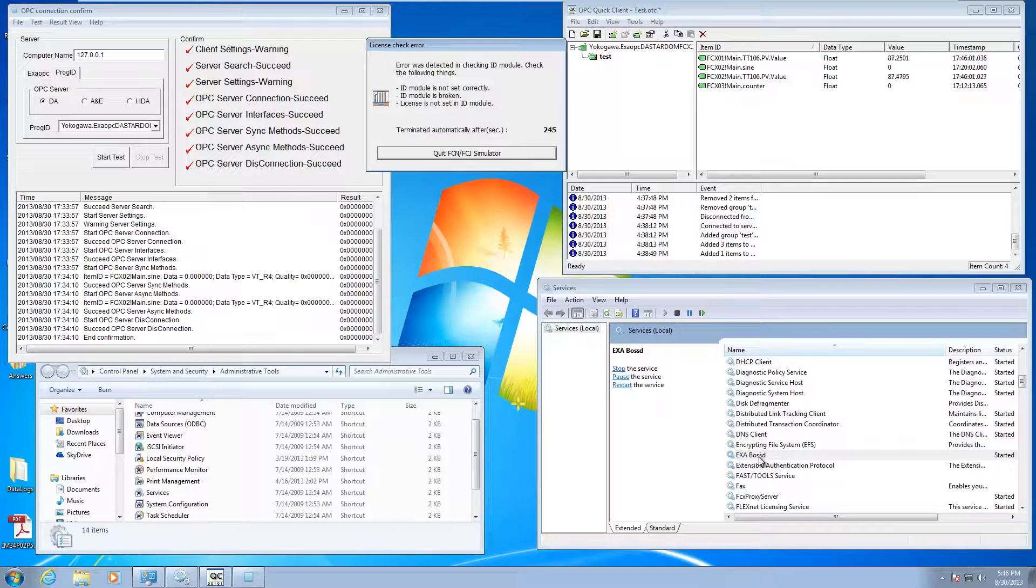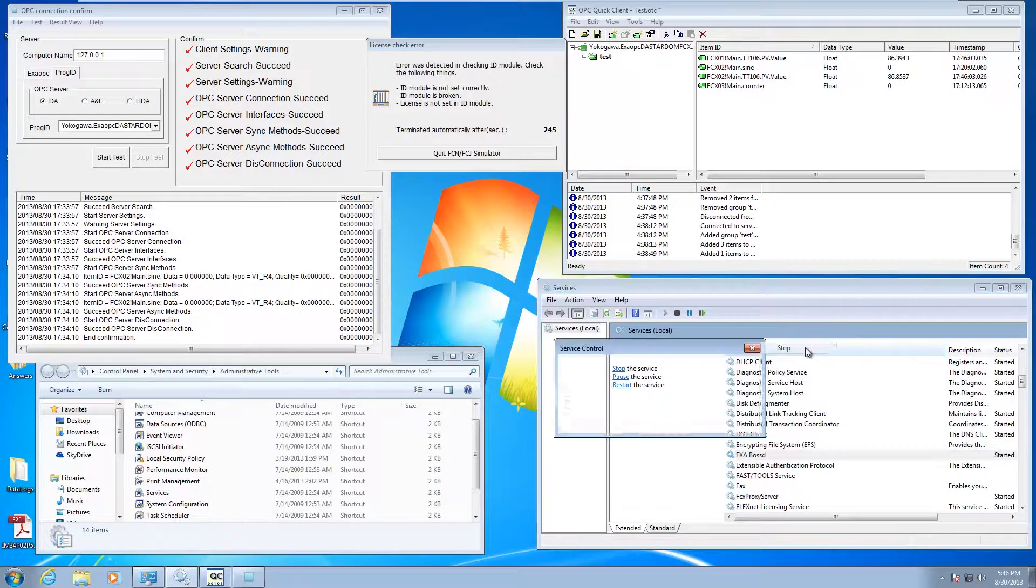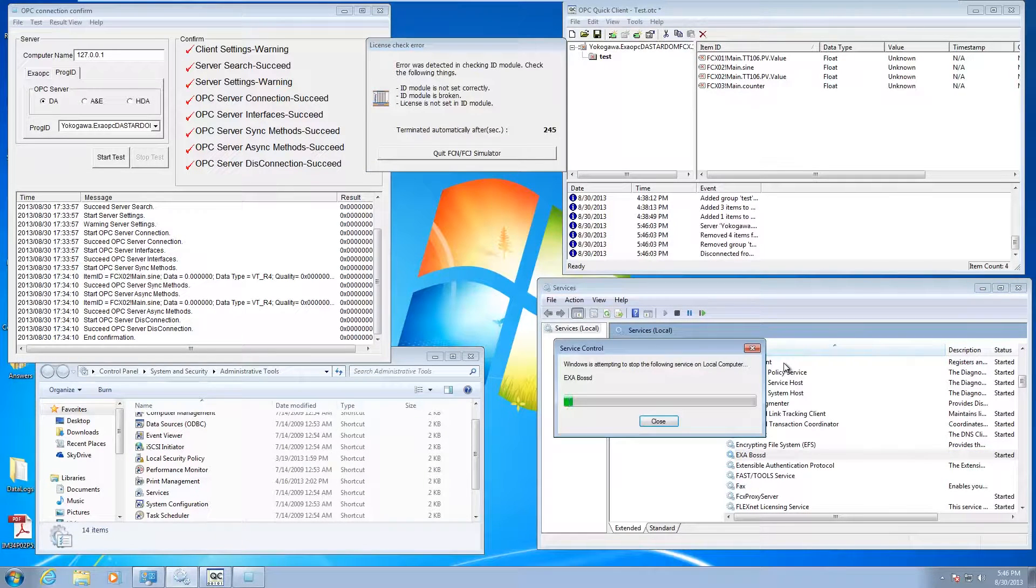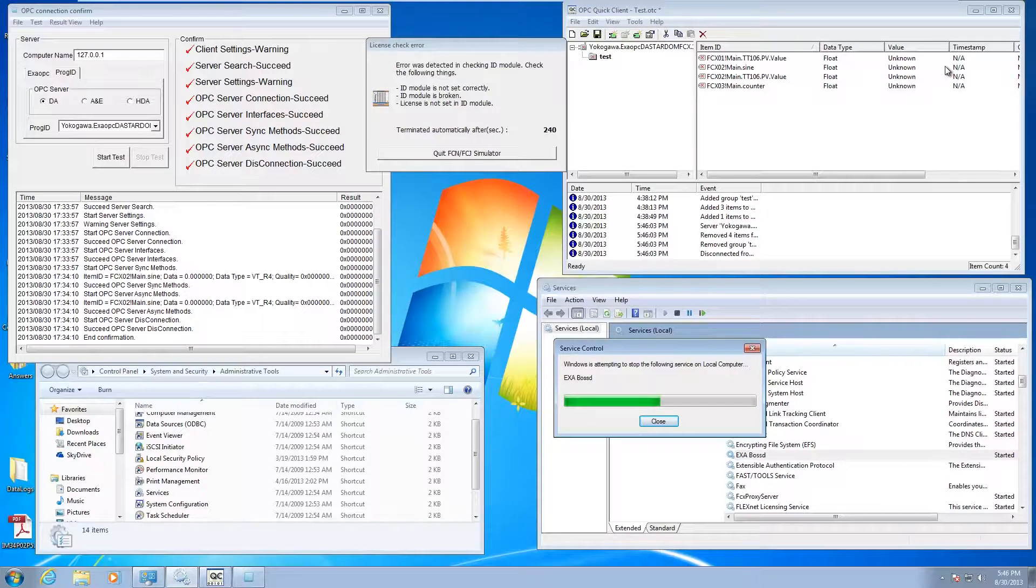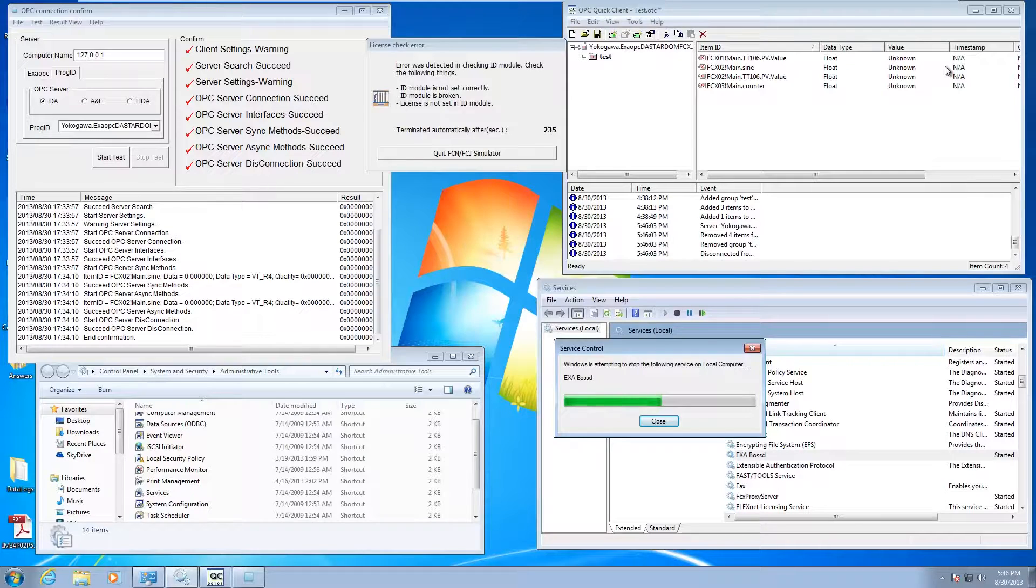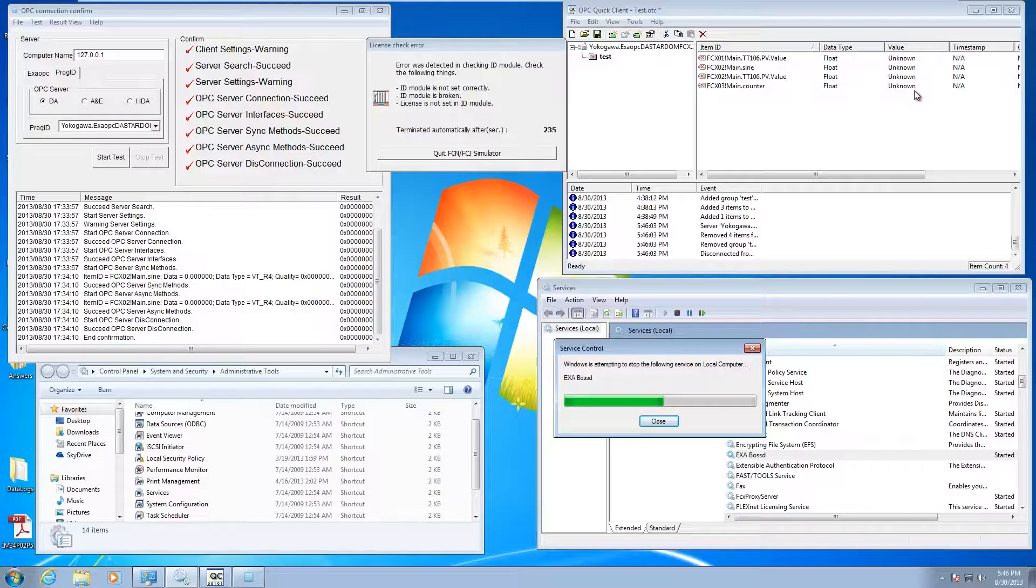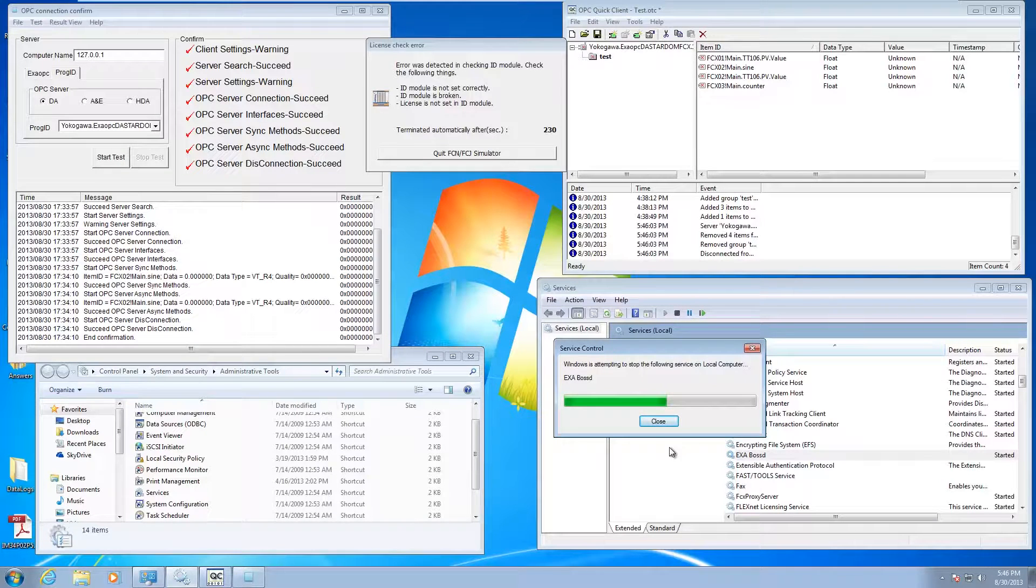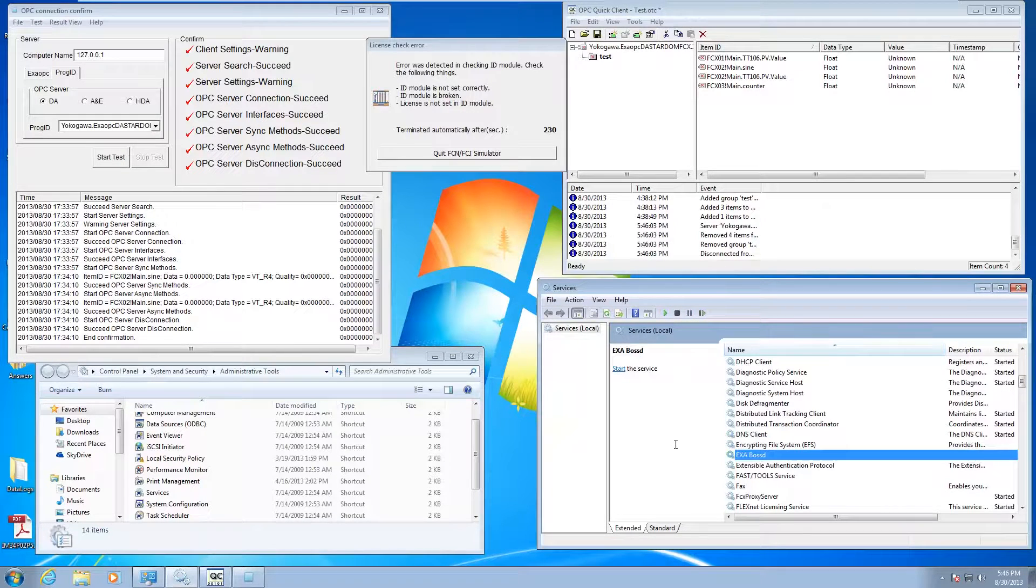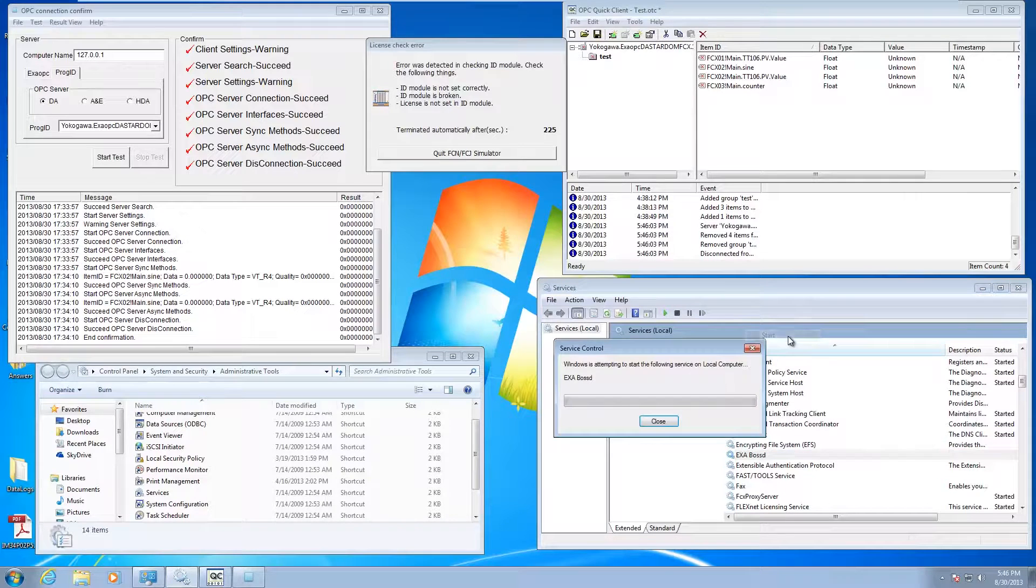Let me show you what that's going to look like here. I'm going to stop it. If you noticed up here, my OPC quick client, everything immediately went offline. If you have any SCADA packages attached to it or OPC clients, you're going to lose the connection. Just be aware of that. But at least it's saving you a reboot.